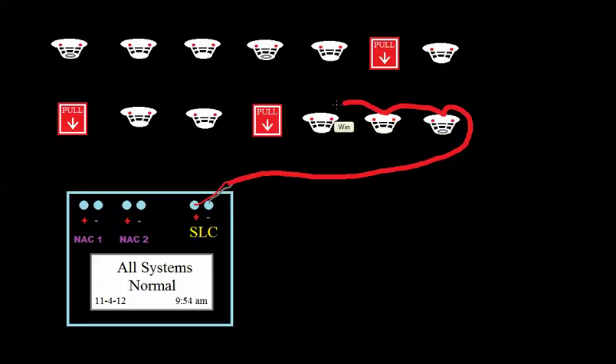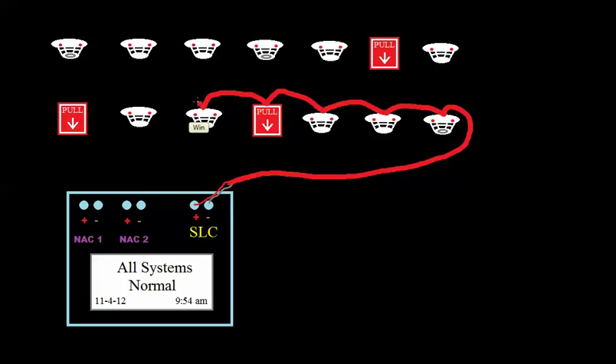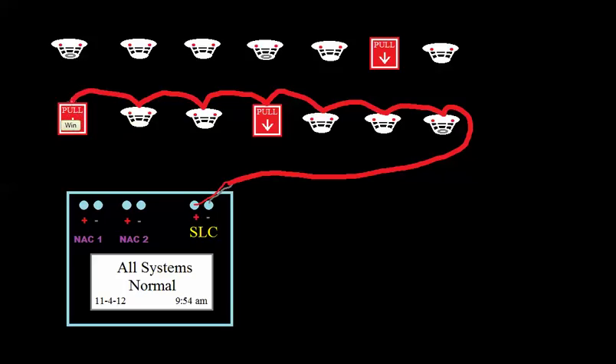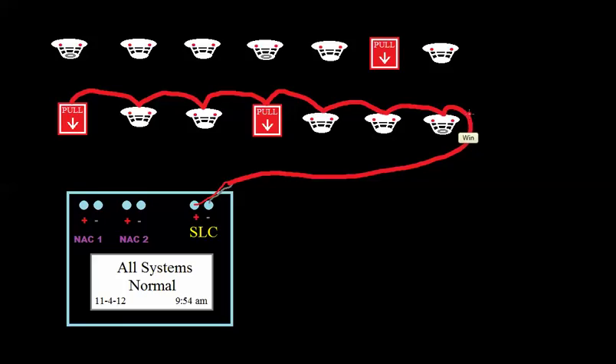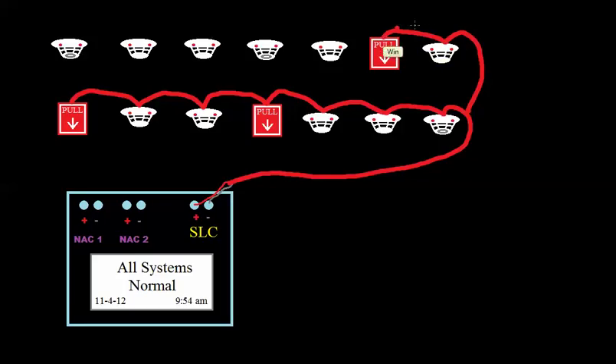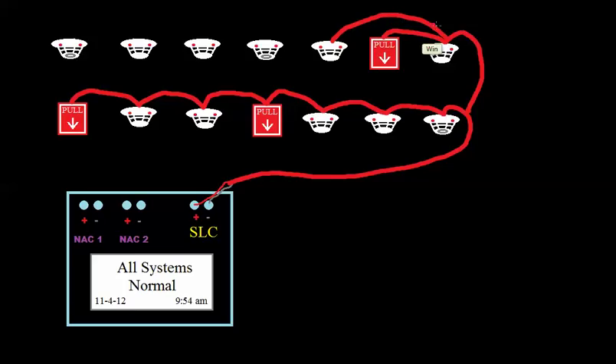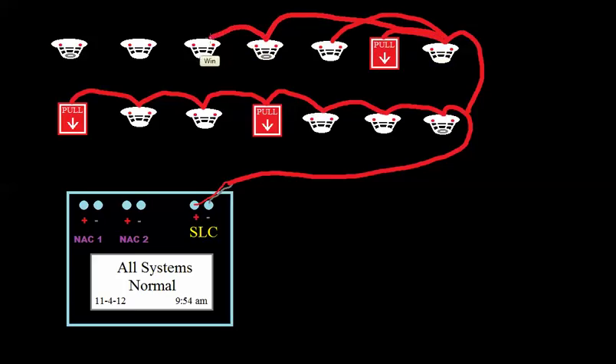I'll just draw this cable, and just imagine that there's a positive and a negative conductor in here. So you can wire this up to each device. Now the way that the panel is going to talk to these devices, remember on the conventional system, it used current monitoring. You'd have the circuit in and out of each device, and then at the end of the circuit, you'd have a resistor. And it was very important that you go in and out of each device all the way to the end. Well, here I can do something called T-tapping. Depending on the style of wiring, there are certain systems where this is not allowed. We'll get into that in the future. Let's say I had a connection here. I could just tap off right here. I could tap off any way I want. I don't have to go in any specific order. All I need is all of these devices to be somehow connected back to that panel.